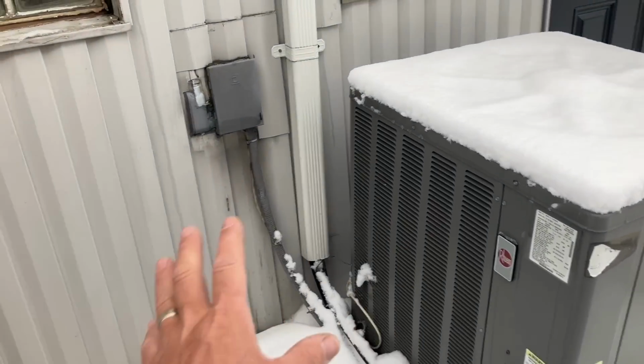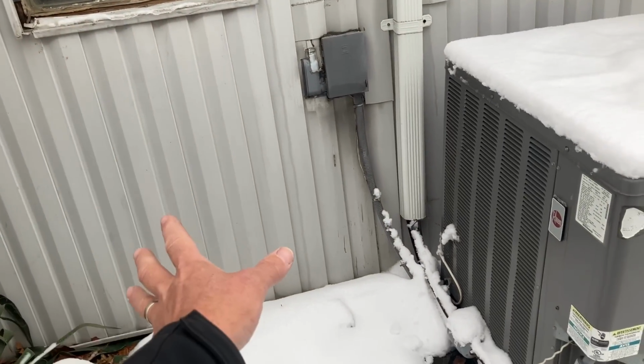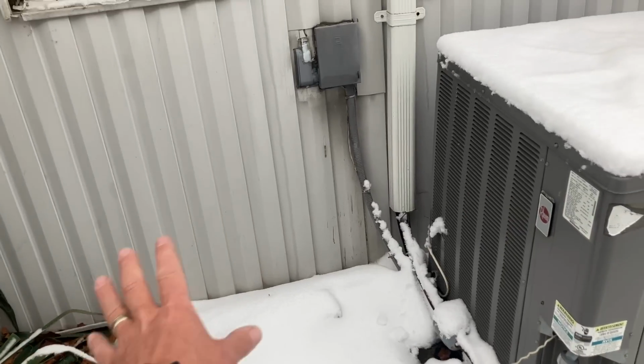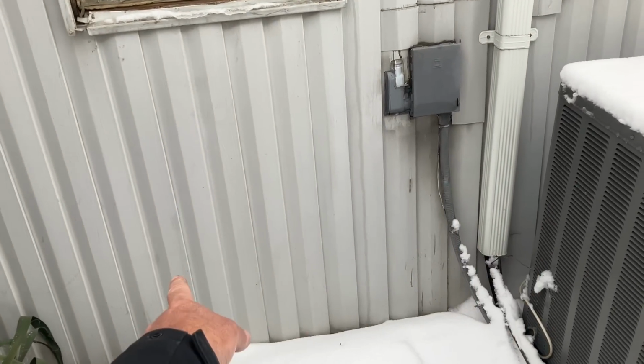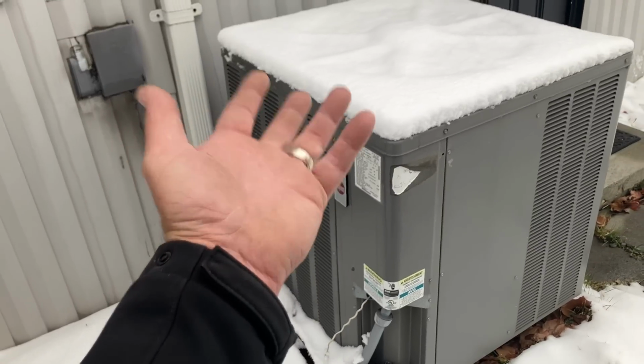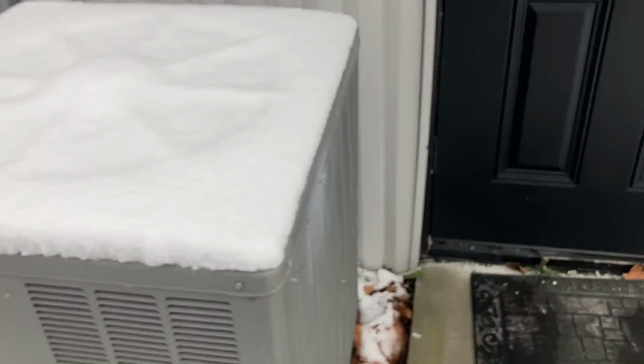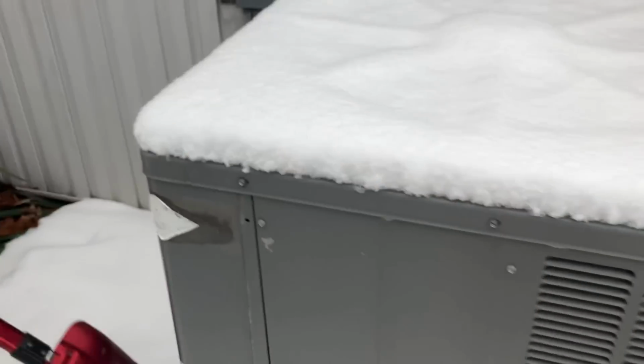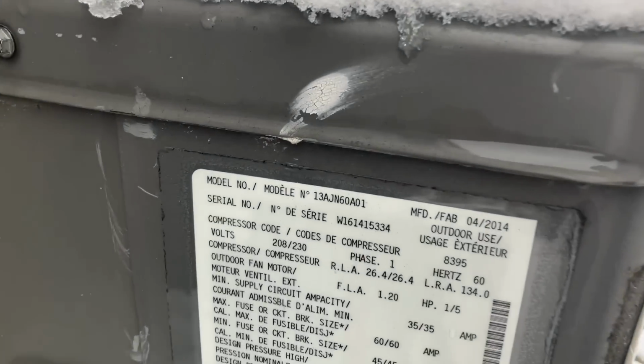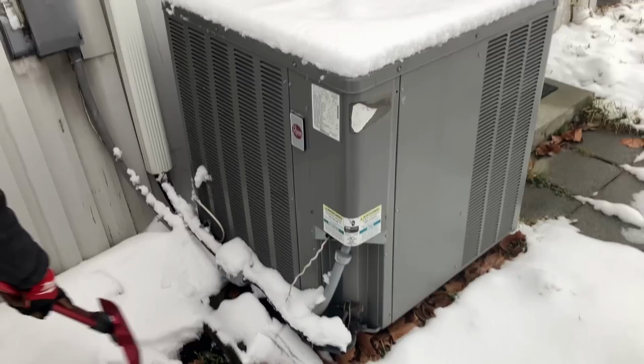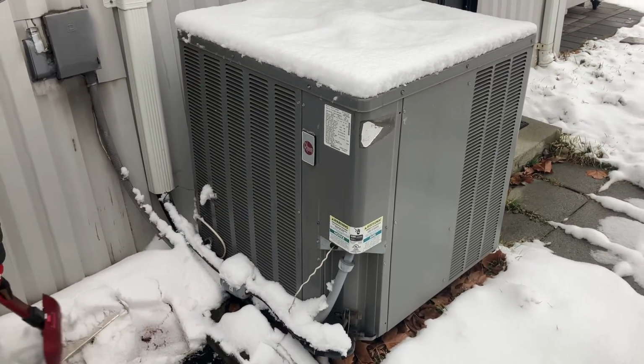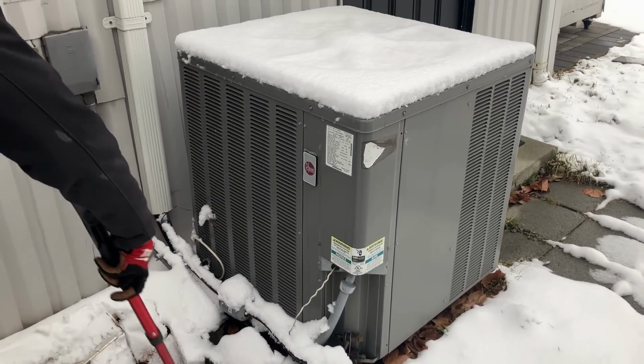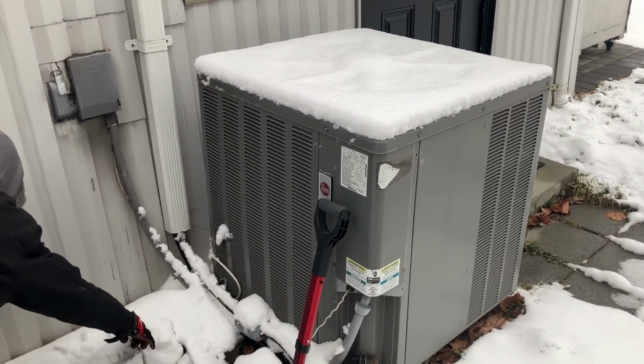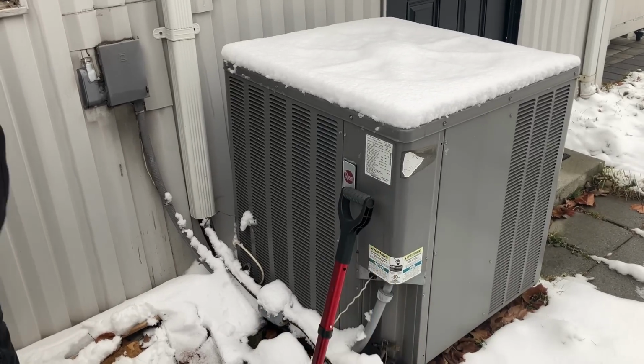We are going to reutilize or repurpose the existing line set to work with our new side discharge condensing unit, which will be outside here. We're going to mount it to a wall-mounted bracket to the wall here, elevating off the ground because it can be used as a heat pump. This unit right here, I think this is a 13 SEER system. Yep, 13 SEER. This is Rheem's builder's grade, central AC system only. Standard compressor, single stage, 1 speed. It's on or off.